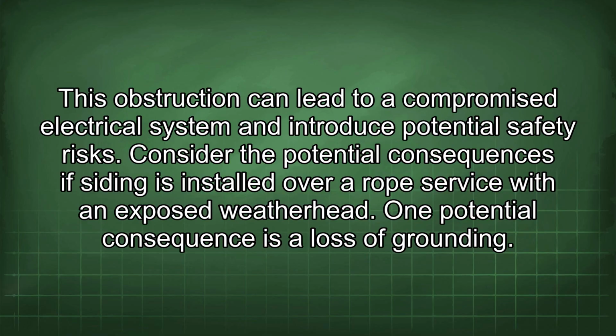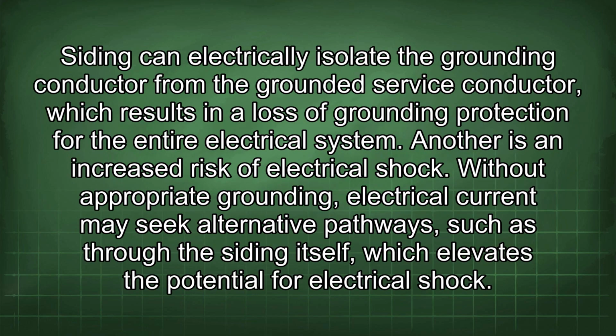Consider the potential consequences if siding is installed over a rope service with an exposed weatherhead. One potential consequence is a loss of grounding. Siding can electrically isolate the grounding conductor from the grounded service conductor, which results in a loss of grounding protection for the entire electrical system.